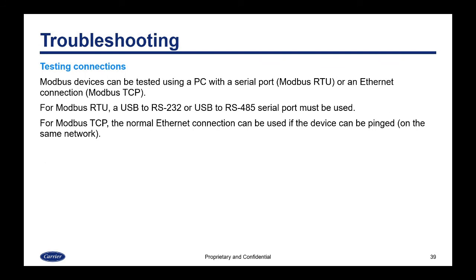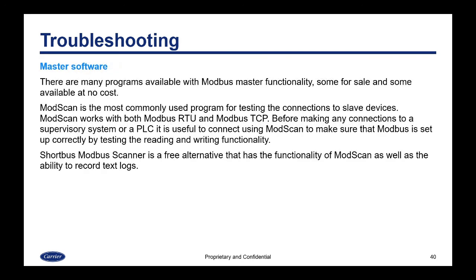When testing a connection, you want to test the Modbus device using a PC with a serial port for Modbus RTU or an ethernet connection for Modbus TCP. For Modbus RTU, a USB to RS-232 or USB to RS-485 serial port adapter must be used depending on whether your Modbus RTU uses RS-232 or RS-485. For Modbus TCP, the normal ethernet connection on your computer can be used if the device can be pinged on the same network. There are many programs available with Modbus master functionality — some for sale and some at no cost. ModScan is the most commonly used program for testing connections to slave devices and works with both Modbus RTU and Modbus TCP.